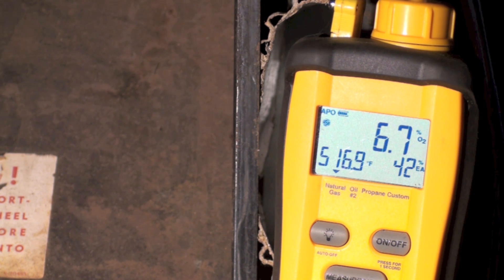Sort of, maybe. Not necessarily, because the other one had a much higher stack temperature - I think it was 570 - but had the same heat exchanger that this one has, just a different tube. The only difference is we've got more primary air in this one, so that's going to cool the flame down. So let's look at some of the rest of the numbers.